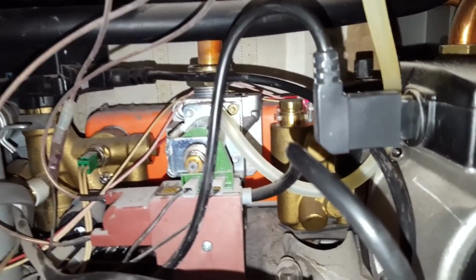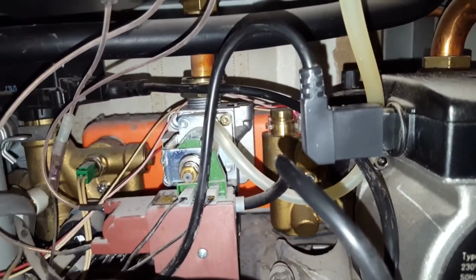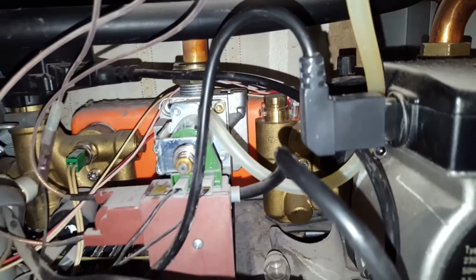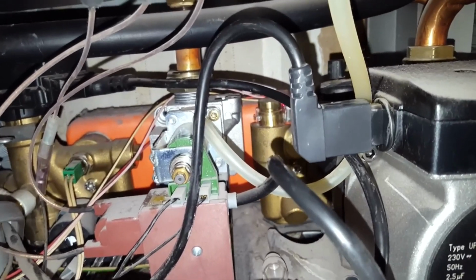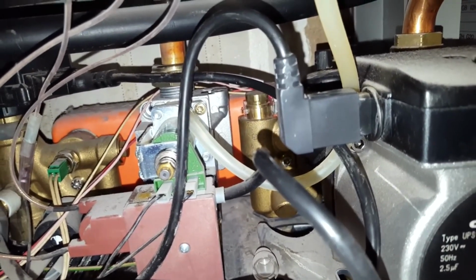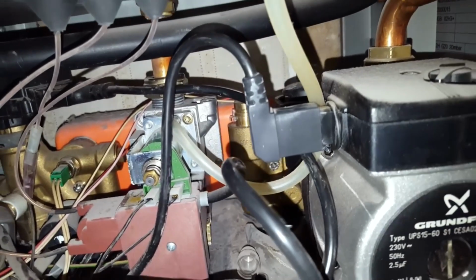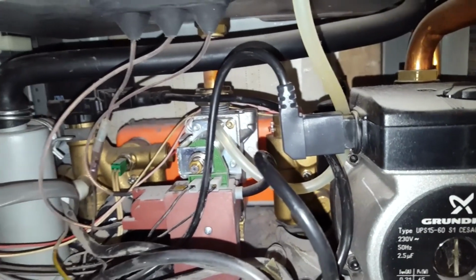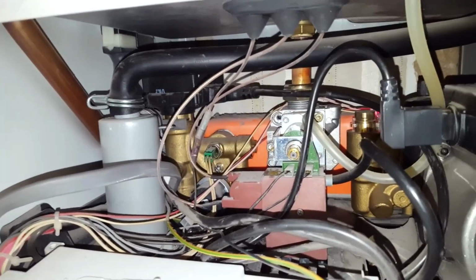So the problem is the flow turbine must be faulty, and it's making the flow sensor energize, go red, put the boiler into hot water mode, and stop the heating from working.